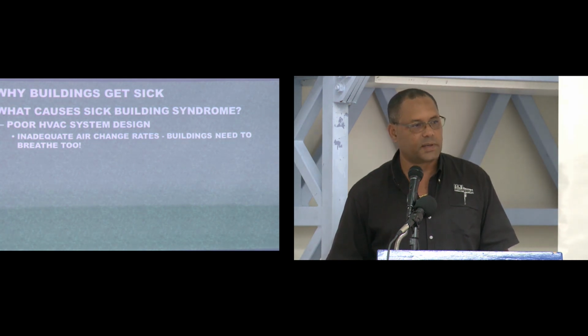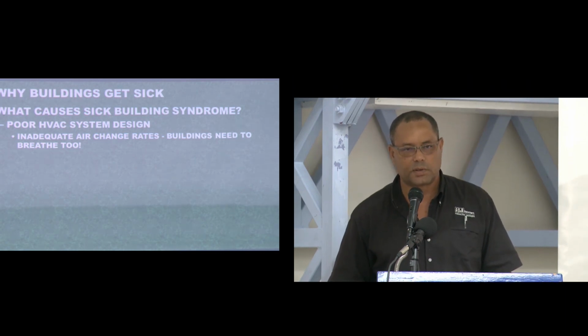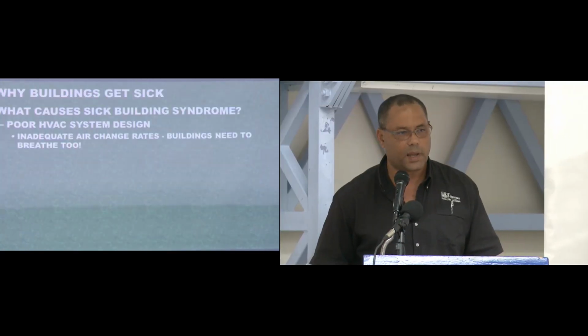And we have passive ventilation systems and active ventilation systems, or positive ventilation. So passive is where you just allow your system to suck air in from the outdoors. And a positive is where you actually have a fan blowing air into your plant room.